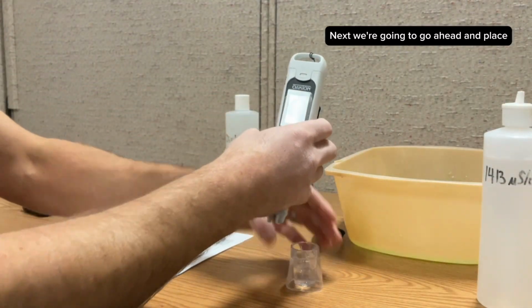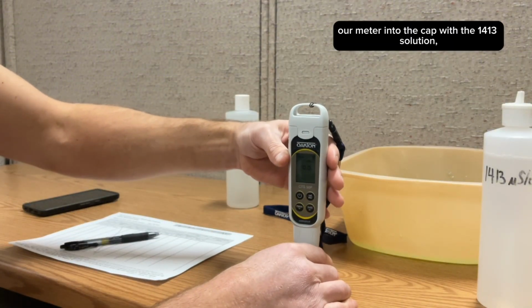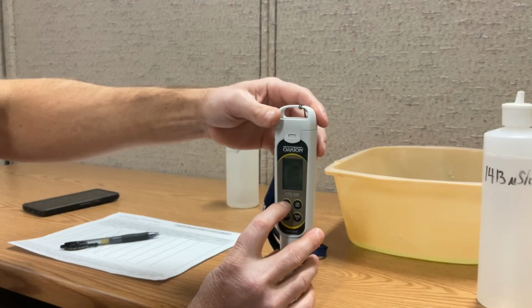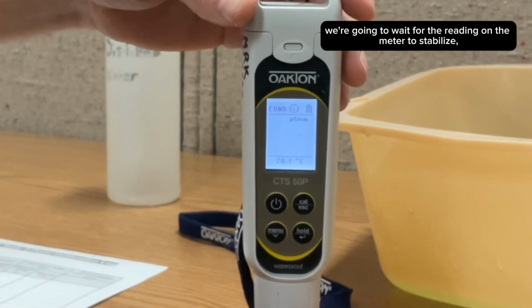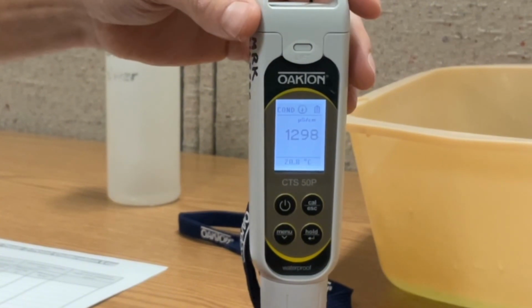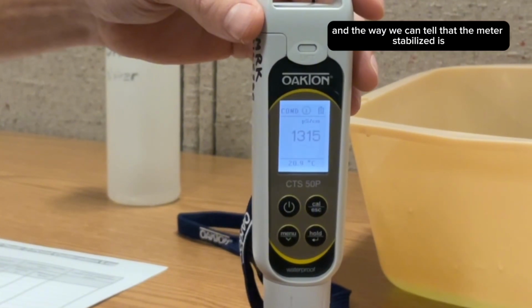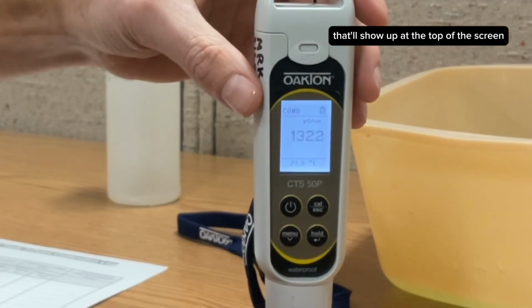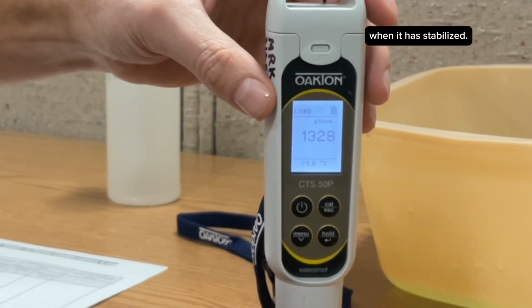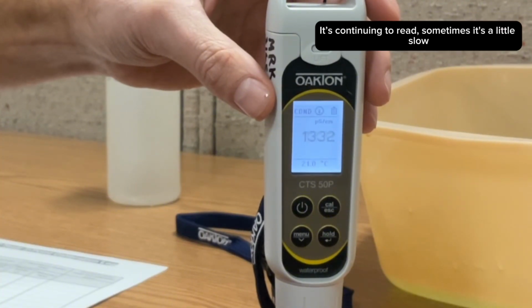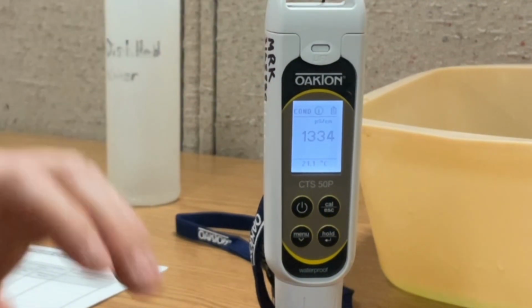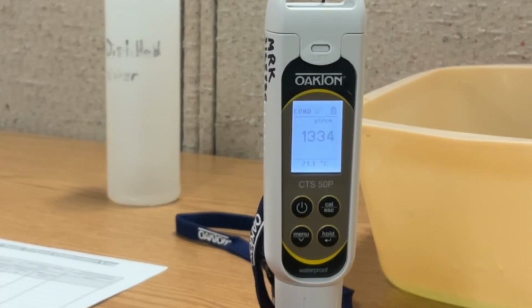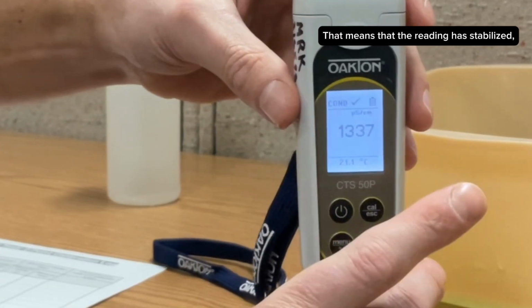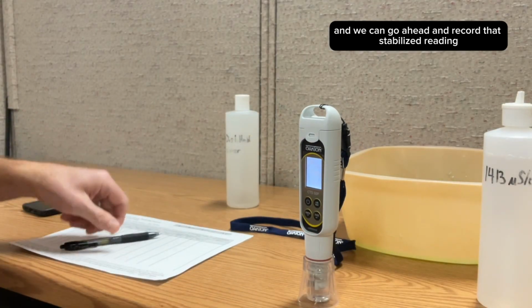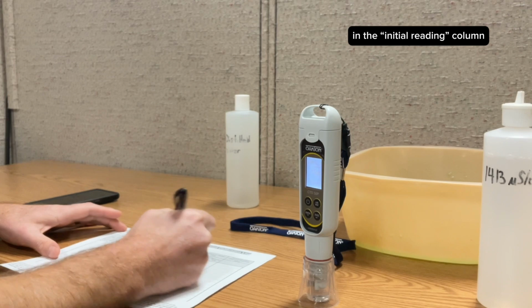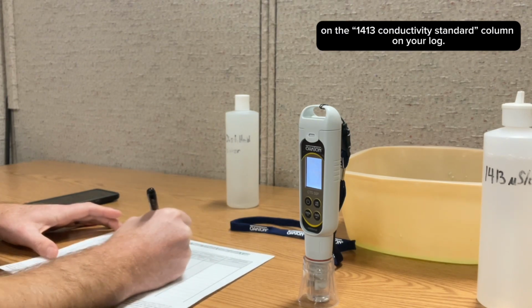Next, we're going to go ahead and place our meter into the cap with the 1413 solution. And you'll notice we're going to wait for the reading on the meter to stabilize. The way we can tell that the meter stabilized is there'll be a small check mark that'll show up at the top of the screen when it has stabilized. Continuing to read. Sometimes it's a little slow, you just have to be patient with it. You can see the small check mark. That means that the reading has stabilized, and we can go ahead and record that stabilized reading in the initial reading column of the 1413 conductivity standard column on your log.